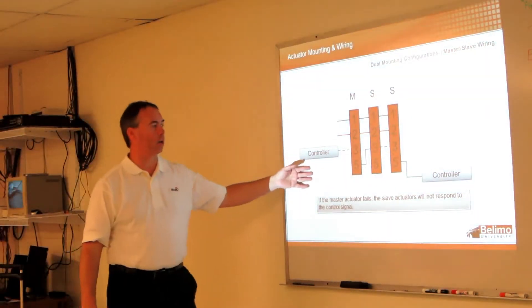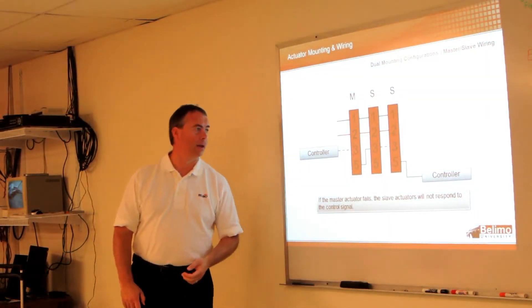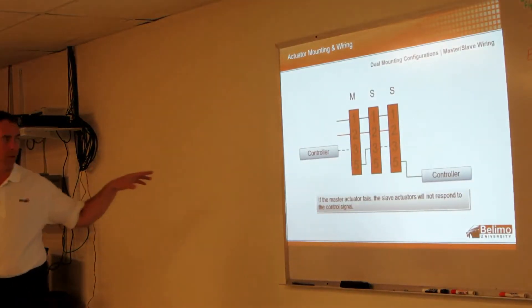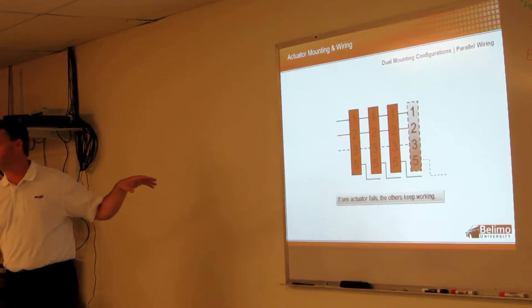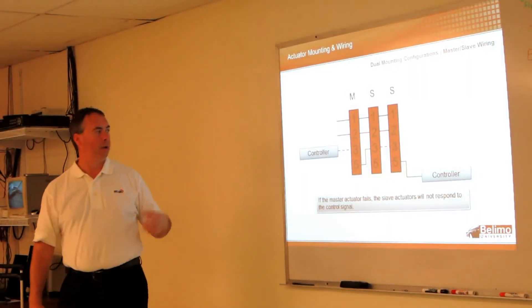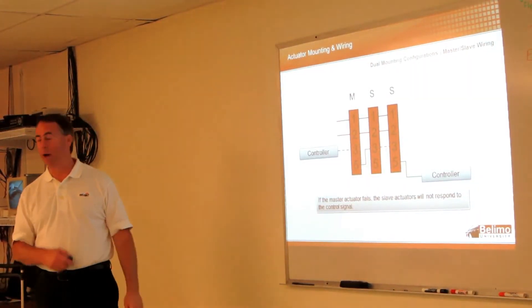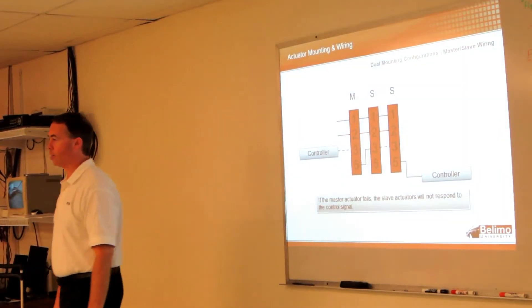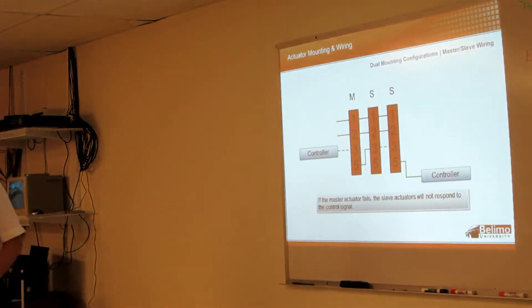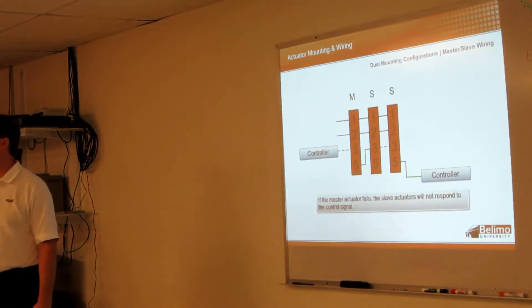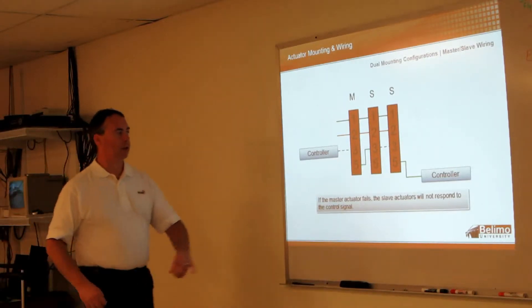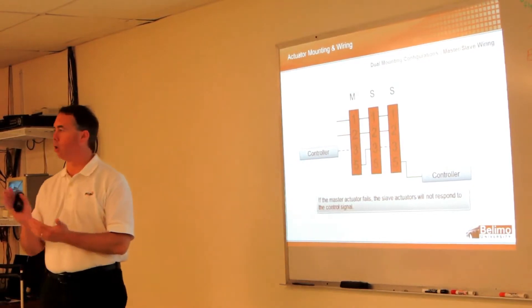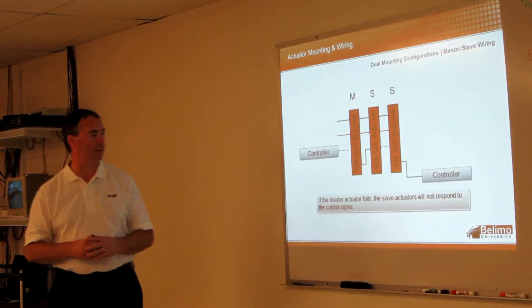Now, this is master-slave wiring, and actually this is the preferred method, if they are both on the same shaft. That other was if they were on multiple shafts. This, if you're on the same shaft, you want to do the master-slave wiring, where you do want to control the other actuators from that feedback, and the reason being you want to keep them in sync. So by taking this feedback wire to this actuator, then it's going to control at the same rate as the first actuator.